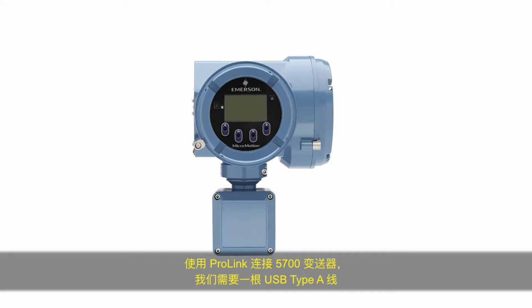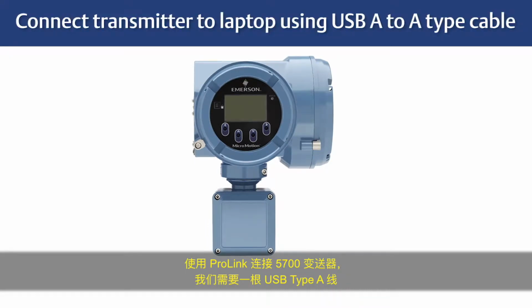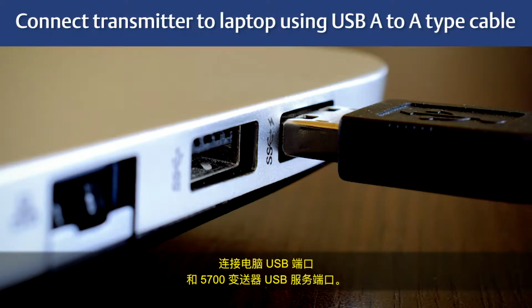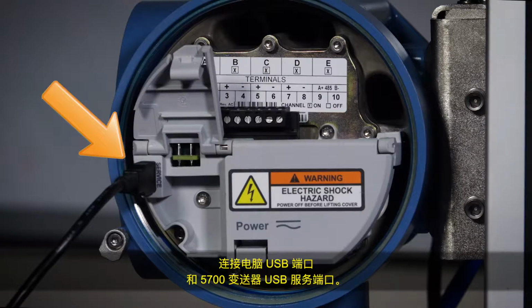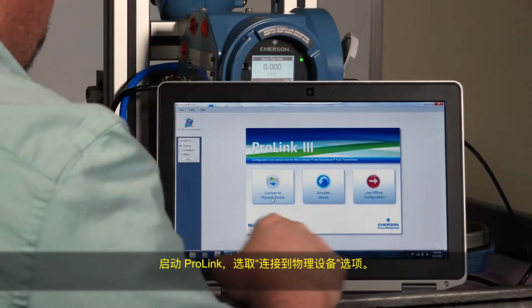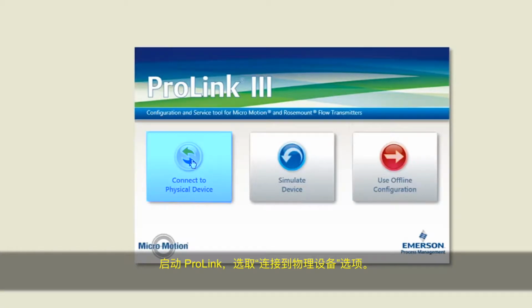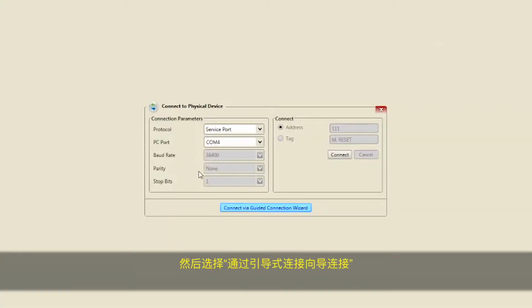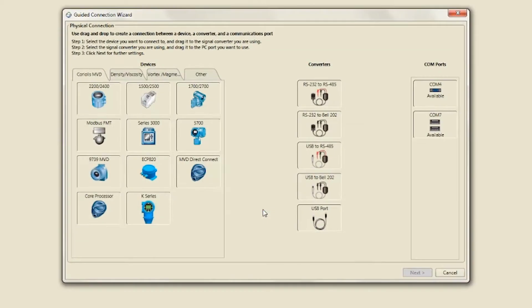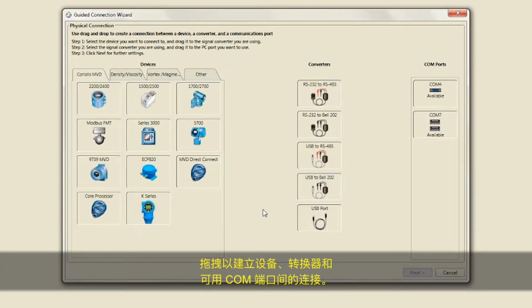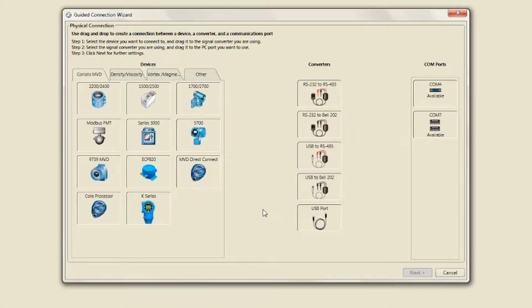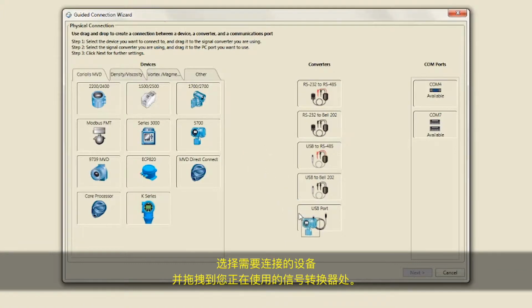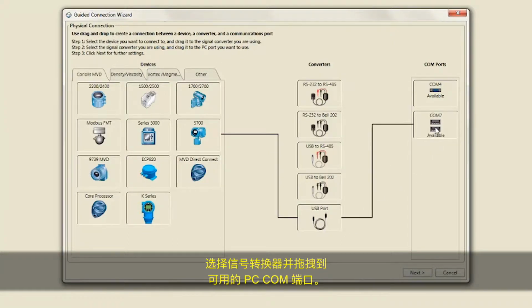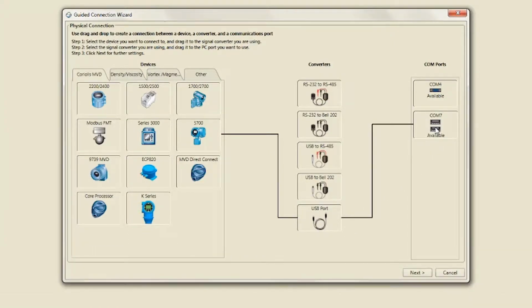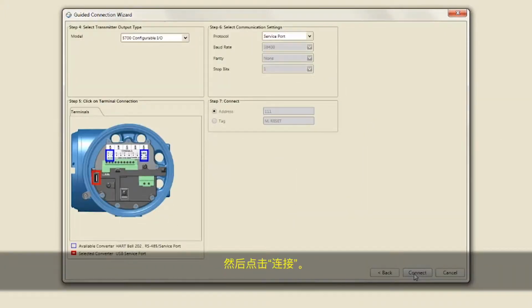Connecting the 5700 transmitter with ProLink, we will need a USB-A type cable and connect from the laptop computer's USB port to the USB service port on the 5700 transmitter. Launch ProLink and select Connect to Physical Device. Then select Connect via Guided Connection Wizard. Drag and drop to create a connection between a device, converter, and available COM port. Select the device you want to connect to and drag and drop the device to the signal converter you are using. Select the signal converter and drag and drop it to the PC COM port that is available. Click Next for further settings. Then click Connect.